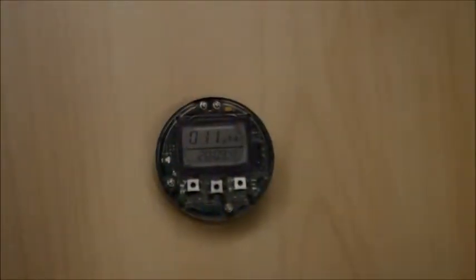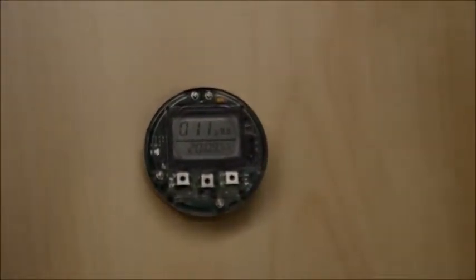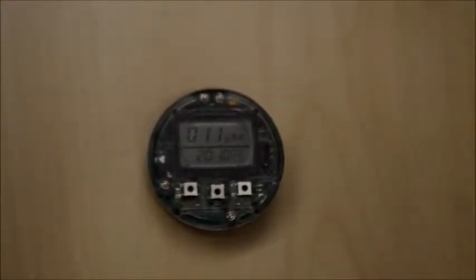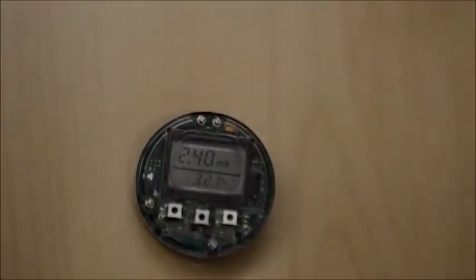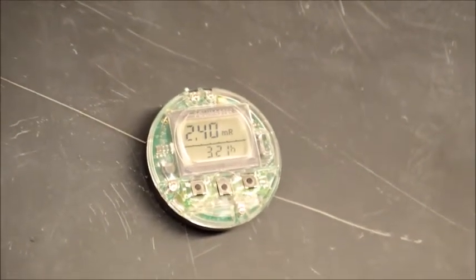This is our gamma radiation sensor, the PM1603B wrist gamma radiation sensor. It is set up in Roentgens right now and has multiple applications. This button allows you to go through each function. The two applications we need are one that measures current radiation levels and one that measures cumulative radiation levels. This button turns on a backlight, and this button turns the infrared transmission on and off. We also have an IR detector that allows us to send information to a computer through infrared light.